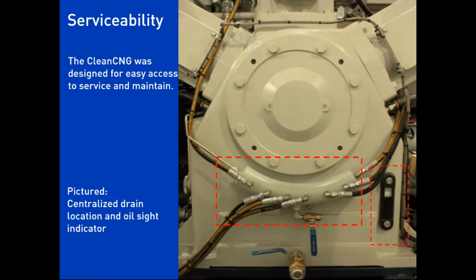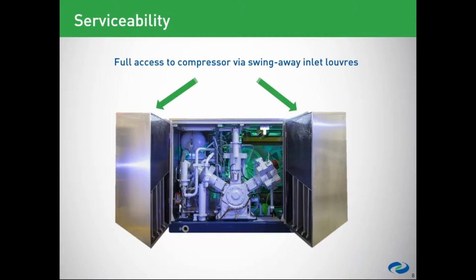So on the serviceability side, we've moved from the vent leg to this vent manifold. We've attached this to the side of the compressor, so it's easy to see, easy to work on, and basically it's a centralized drain location, so we can drain the vent manifold and the compressor if need be. And this is by opening the louver doors, so the inlet louver doors. The side of the compressor is facing you immediately as soon as you open those doors. So you don't have to get in to work on this.